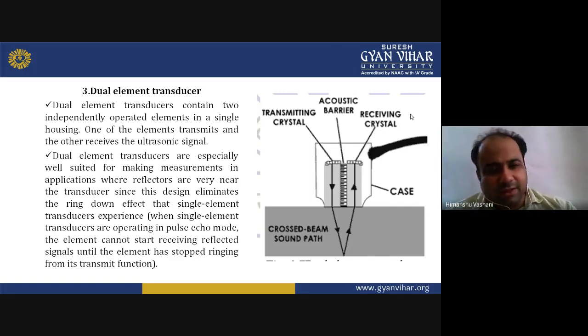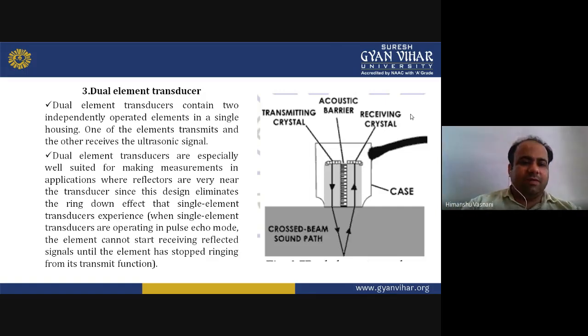Now what happens in single element transducers? These single element transducers operate in pulse echo mode. Due to this, the element cannot start receiving reflected signals until the element has stopped ringing from its transmit function. So when there is a single element transducer, the reflected signals cannot be received properly. So we go for dual element. These make the applications and measurements comparatively easier, because they avoid the ring down effect that the single element transducer experiences.